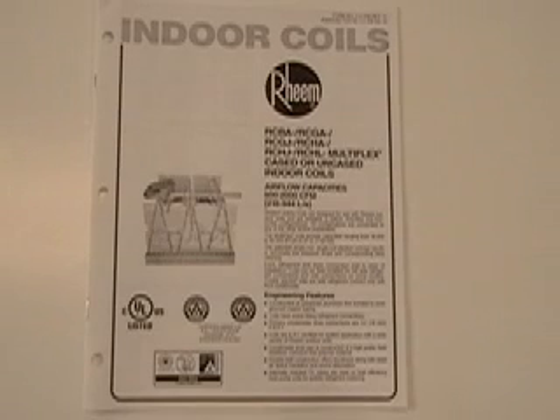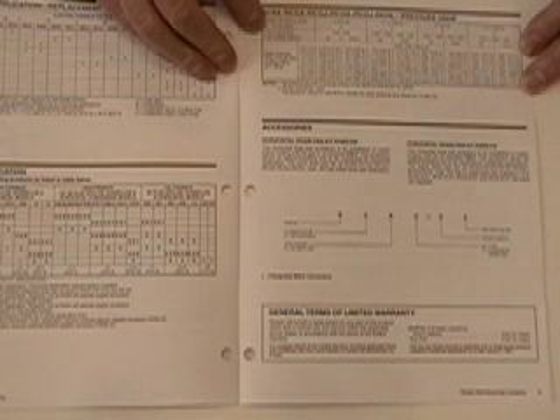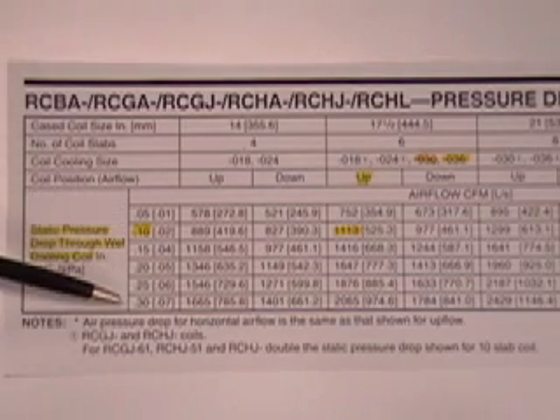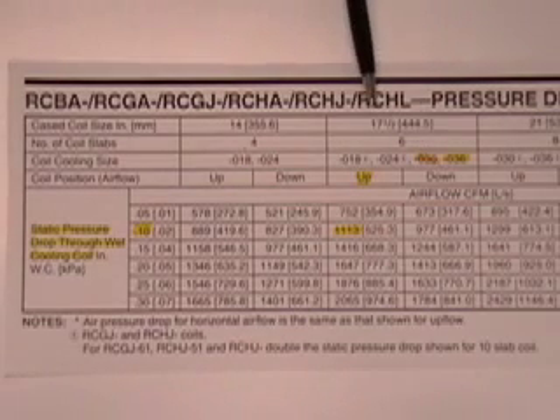Here's a spec sheet published by the manufacturer of this brand of evaporator coils. Looking inside, we can see that this manufacturer has conveniently provided a pressure drop chart showing airflows at various pressure drops through their coil. These are very accurate, and we can use these in the field to make accurate measurements of airflow with our Magnehelic gauge. They have indicated the various pressure drops that occur at various CFMs for different sizes of coils. The coil we have just measured is a 2.5-ton coil in a 17.5-inch cabinet.